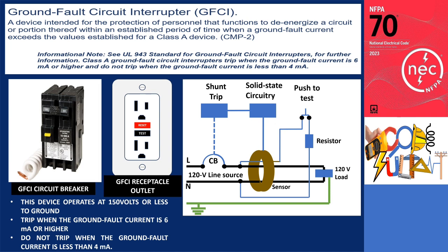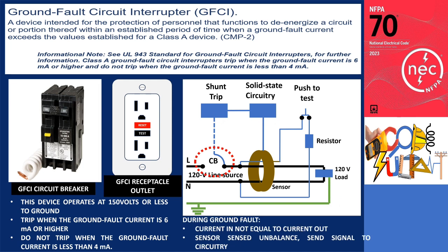How does a GFCI work? Shown is the typical circuitry and components of a GFCI. During normal conditions with no ground fault in the circuit, the current in conductor L is equal to the current in conductor N, and these conductors are passed through the sensor. This sensor monitors the current in conductors L and N, and is also connected to a shunt trip. In case of a ground fault, there will be a current in the grounding conductor that results in an unbalanced current. The sensor will detect it and send a signal to the shunt trip to shut off the power, and GFCIs can significantly reduce the chances of electrocution.